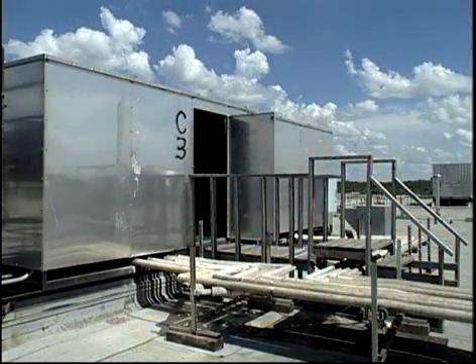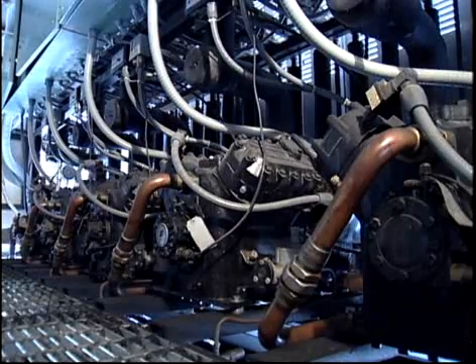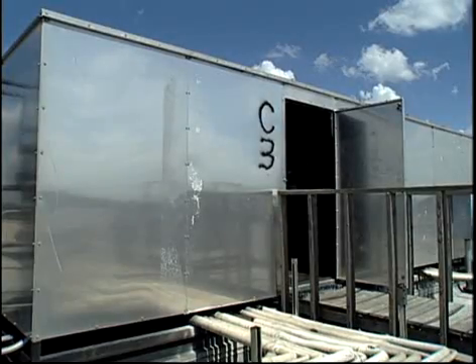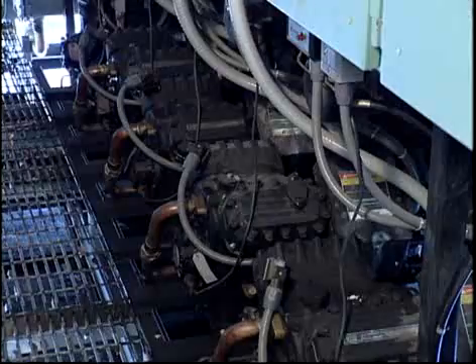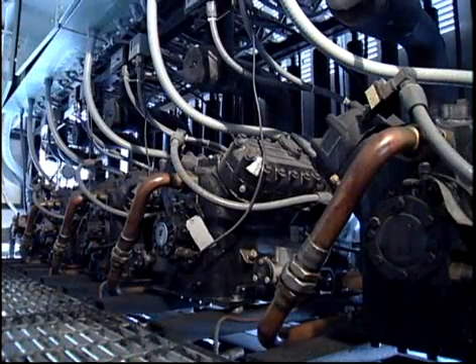The compressors are grouped together in these rack shacks for convenience, safety, economy, protection from the weather, and in general a more technician-friendly environment. And speaking of friendly, these compressors have all been retrofitted to use the more environmentally friendly HFC-R507 coolant, instead of the ozone-depleting CFC-R502.